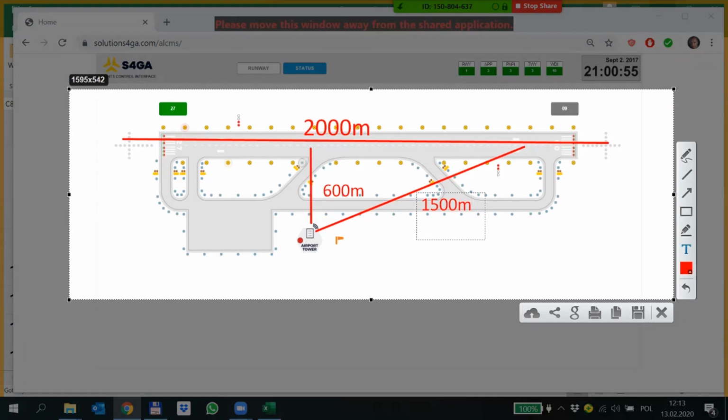So the thing is how our radio operates. The control unit sends the signal to all the lights it sees. So let's say this is a radius of 1.5. Everything outside of the radius of the control system, the question is, how will the signal reach there? Because it's a mesh network, the signal will jump from light to light. Each light is a transmitter and receiver, so the signal will be retransmitted to all the lights, even though they might not be visible to the control unit. This is why we don't need 1.5.